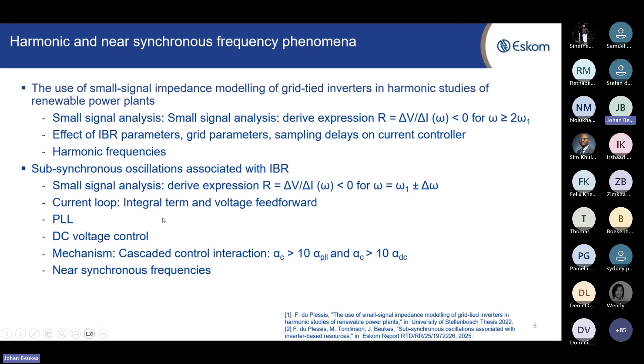Then you get subsynchronous oscillations associated with IBR, and there are two categories of these subsynchronous oscillations. You get the near synchronous frequency oscillations, and then the low frequency oscillations. For the near synchronous frequency oscillations, the PLL and the DC voltage control loop inside the inverters play an important role. So PLL parameters and DC voltage control parameters are important to set. But the one that I want to look at today is the low frequency, because that is the one aspect that we suspect is causing most of the issues at the moment on the grid.